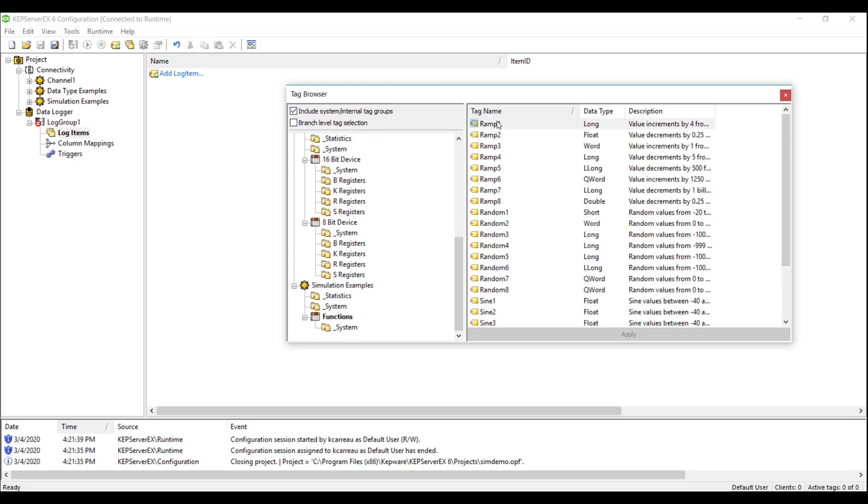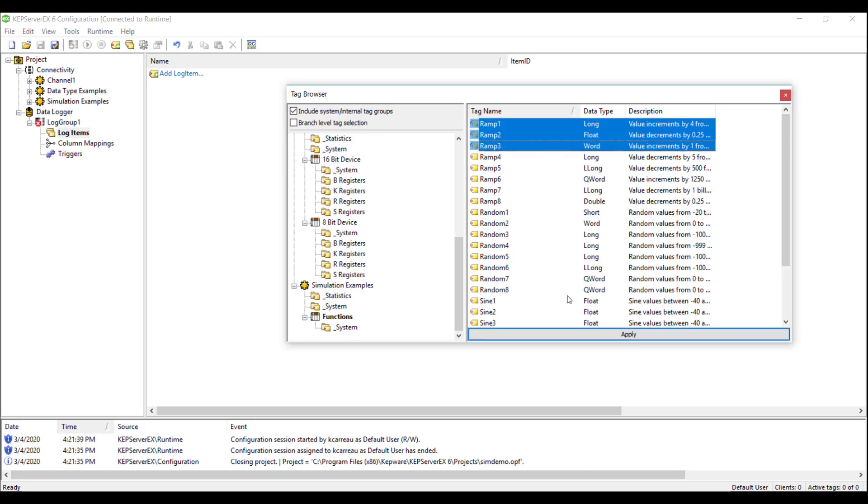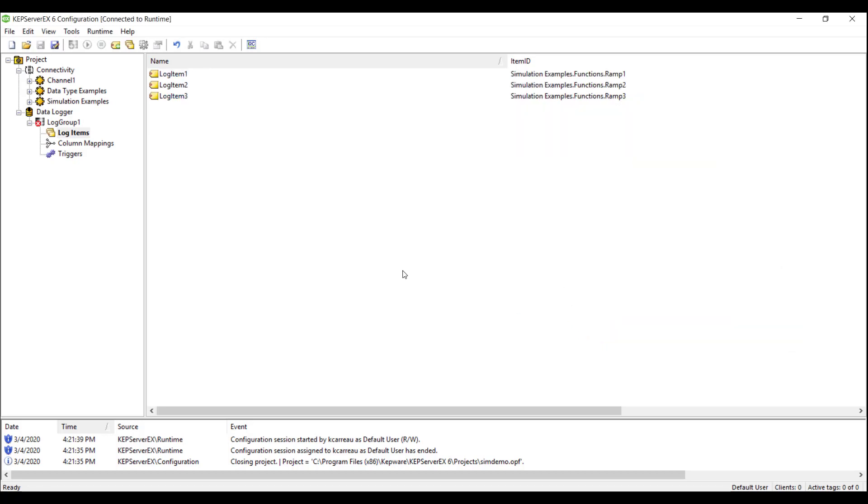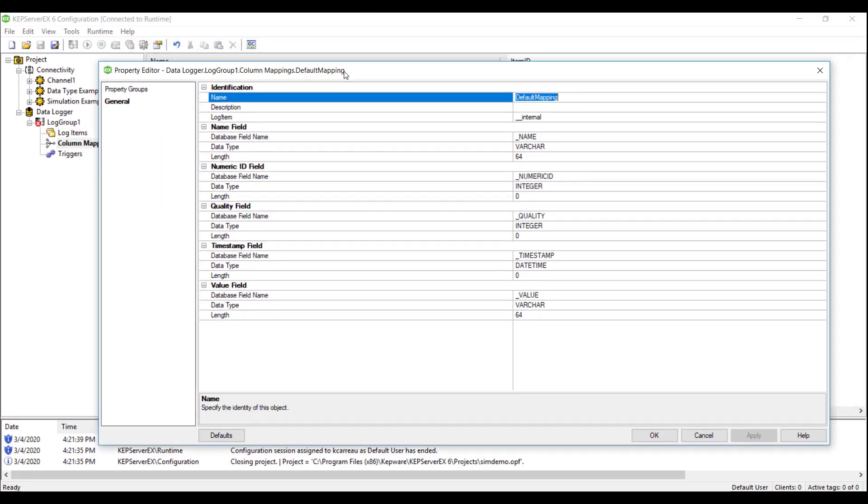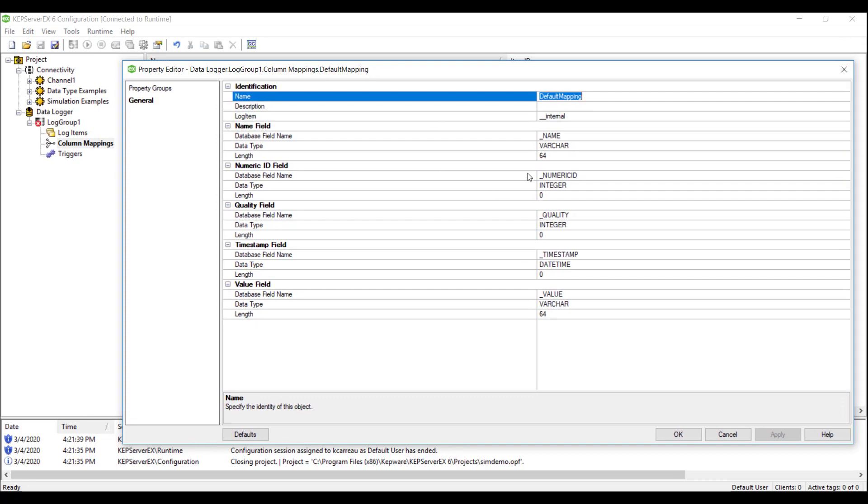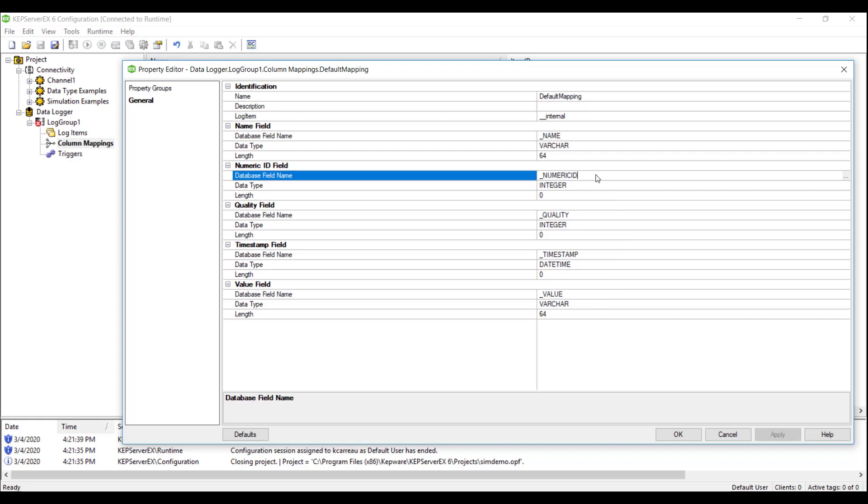The next step is configuring the column mapping. The column mappings are used to specify how the properties of the log items are mapped to the columns of the database table. The default configuration of the column mapping should be sufficient for most applications. For this demo, we will be deleting the Numeric ID field. This property acts as a numeric alias for the tag. There are applications where this could be useful, but for this demo we want the SQL table to show the name, value, quality, and timestamp of our tags only.